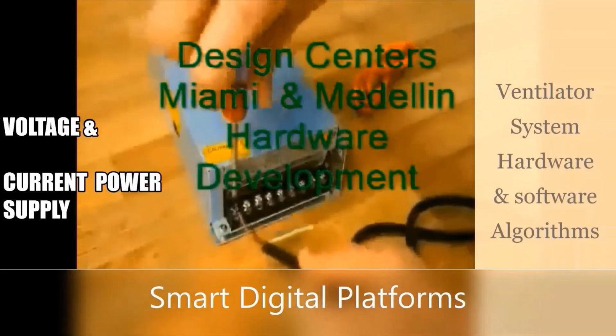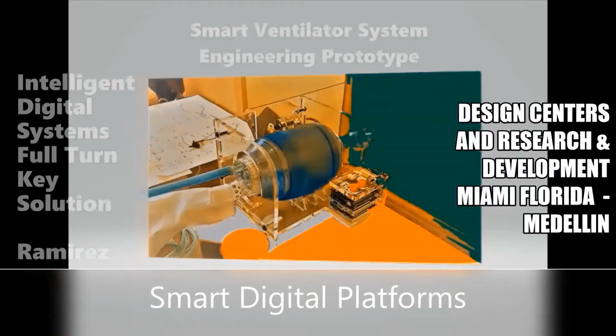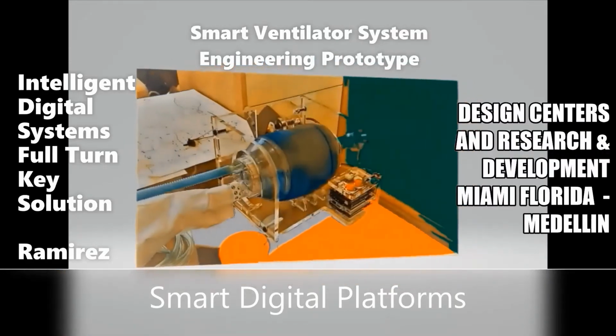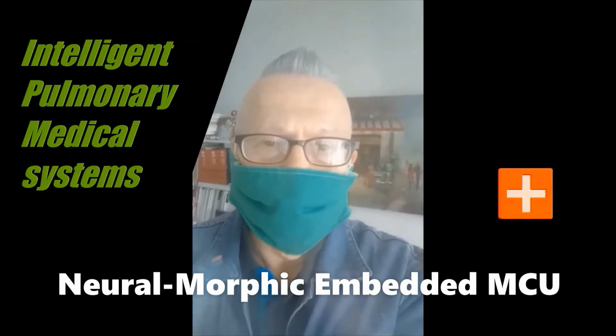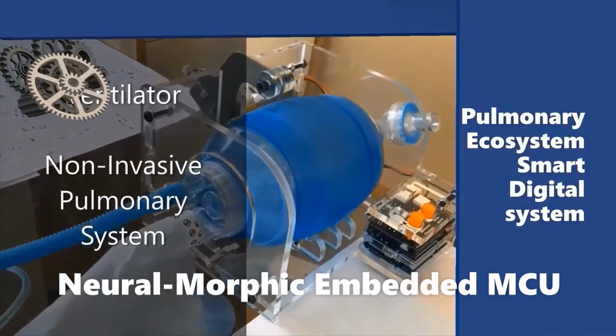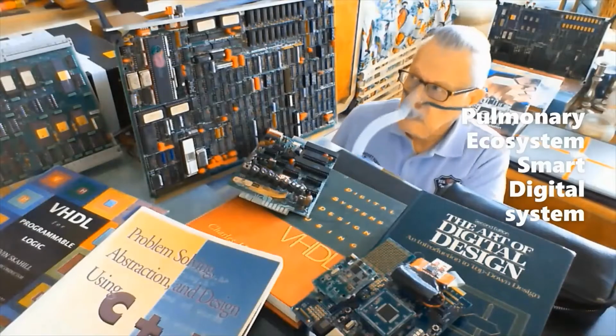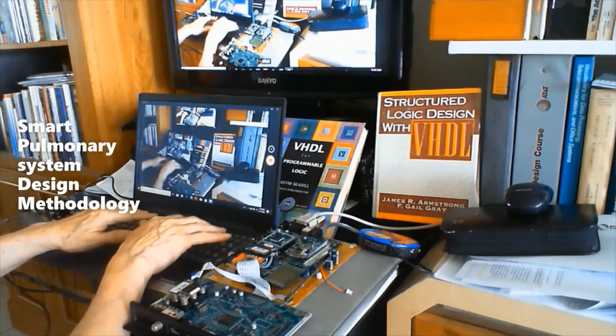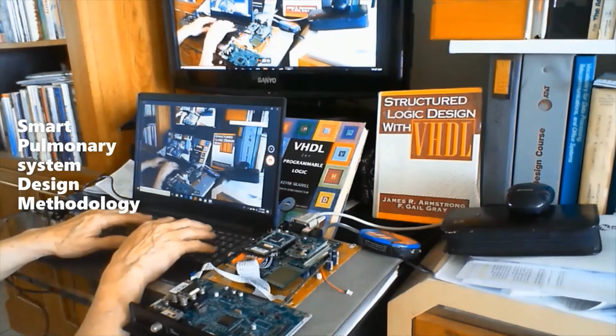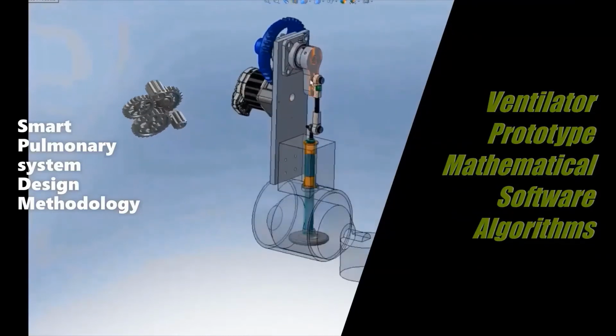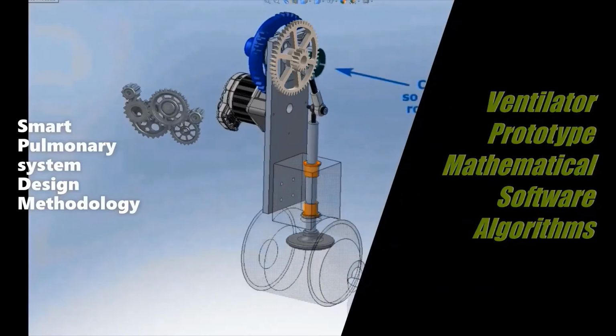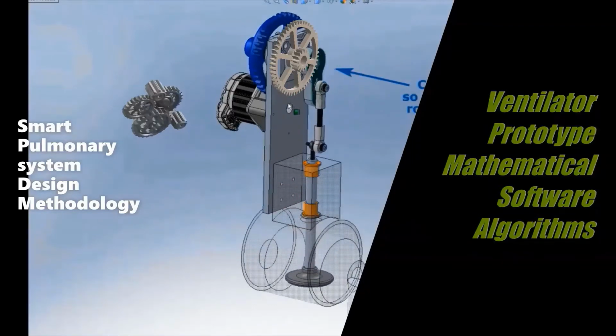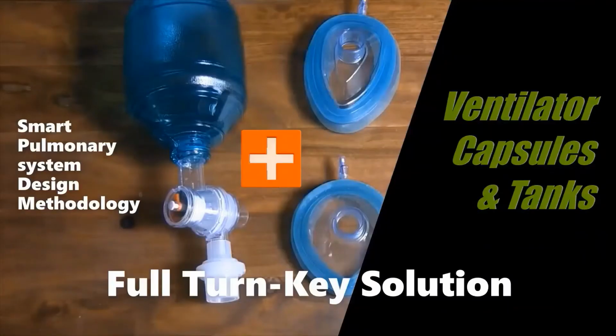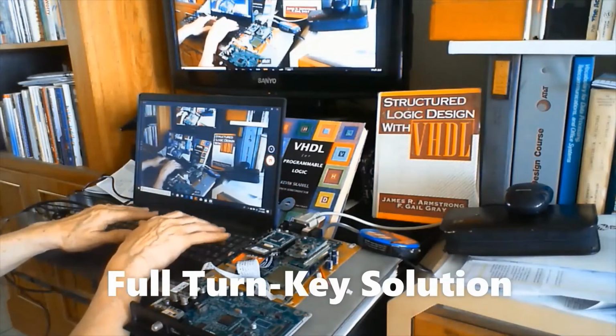The Neural-Morphic embedded microprocessor allows the implementation of sophisticated signal processing of the measurements provided by sensors, leading not only to better measurement accuracy and better rejection of noise and artifacts. It also deals with the generation of new information by appropriately computing and integrating several variables. These variables expand information that can be used by the ventilator to optimize the ventilation parameters.